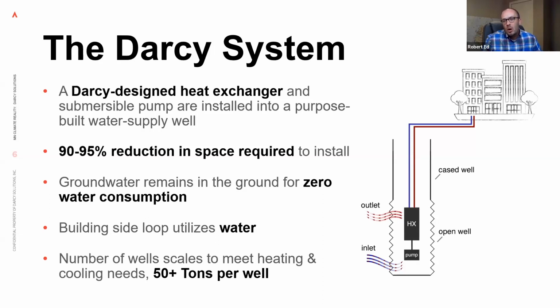So it's a big circuit of water continually pumped over time, and that's how we provide thermal exchange from the groundwater up into the building. The groundwater we use to cycle across the heat exchanger is not brought up to the top of the well, it's all left down in the aquifer. We're simply trying to access the thermal mass of the substrata, and using groundwater means we get access to significantly more thermal mass. That's why we can produce significantly more capacity from these water wells than traditional geothermal borings, which are smaller in diameter and not necessarily able to use all that groundwater to access the mass.